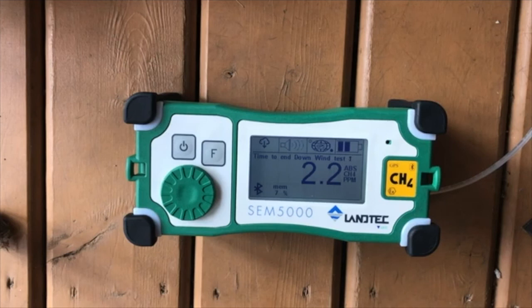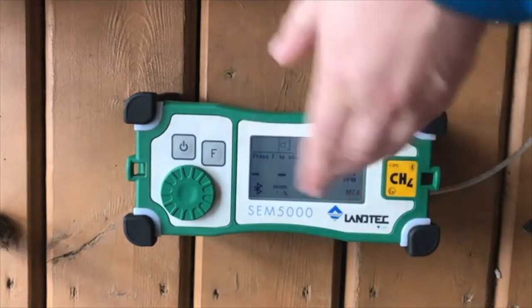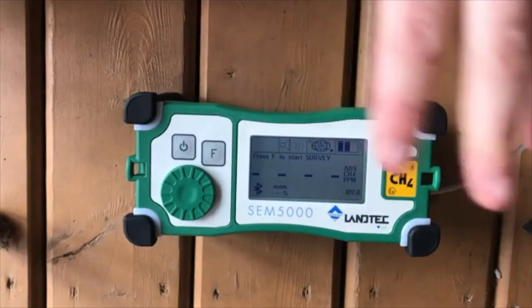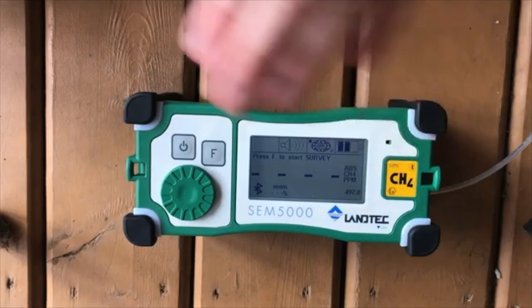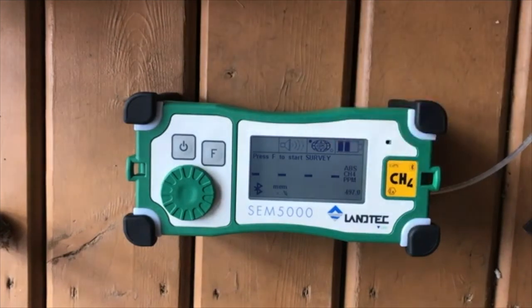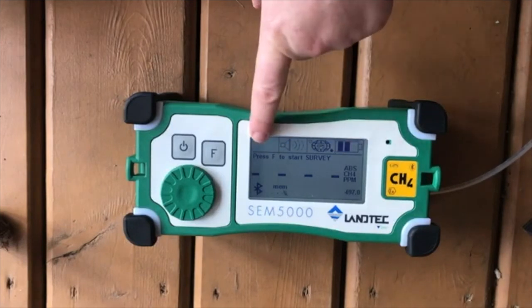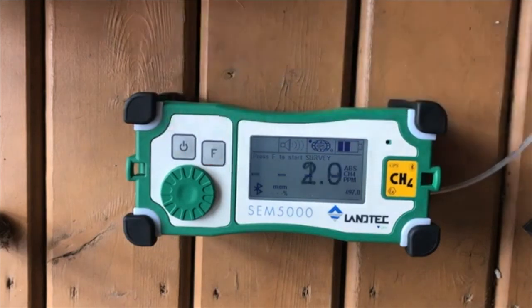So this value, 497, is now our background exceedance level. It is not 500 as the upwind and downwind test incorporated the background methane present on the site. And the other value is an average of the 3 air and the 3 gas tests that you completed. So at this point, you have completed your field calibration. Once you're at the initial starting point for your scan, simply press F to begin your scan.